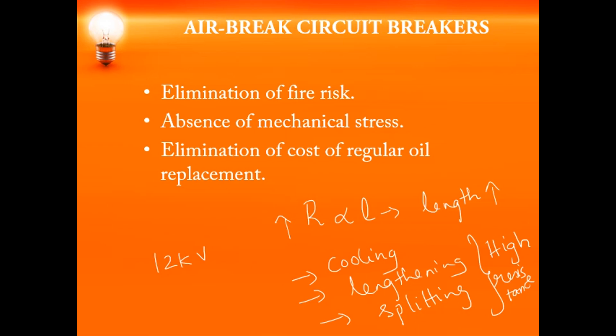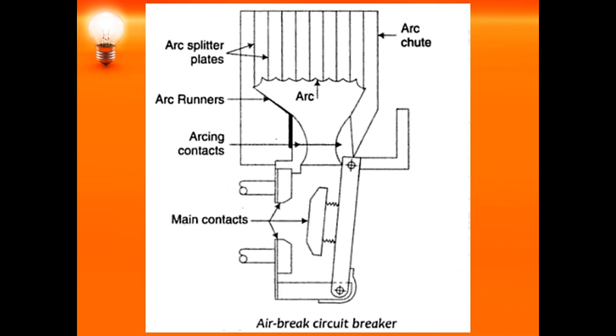Now let us see the arc chute type air break circuit breaker. As you can see in the diagram, this arc chute type circuit breaker has mainly the main contacts and the arcing contacts. You also have the arc runners on both sides, and the vertical lines are called arc splitter plates. Together these form the arc chute.